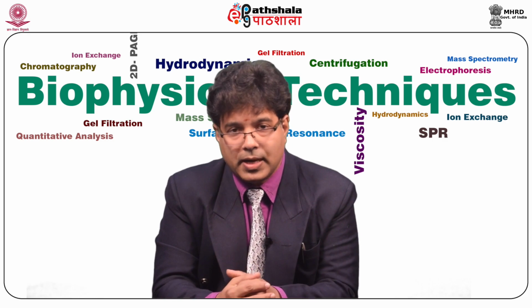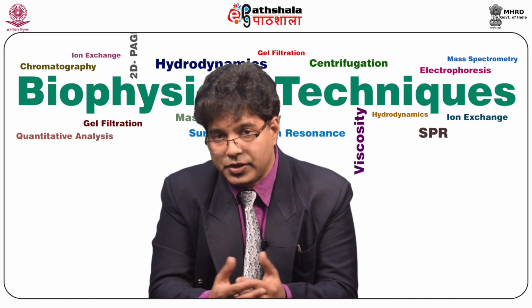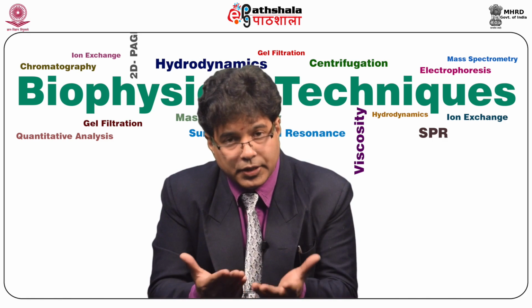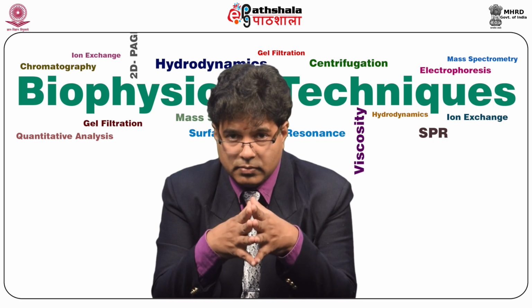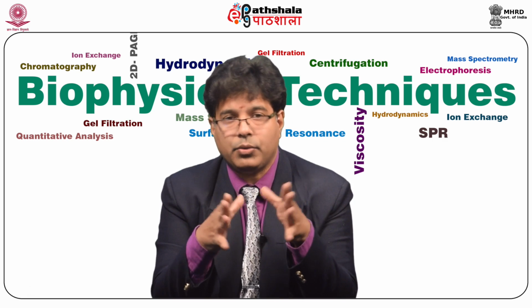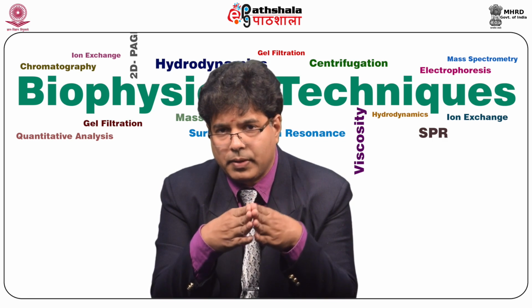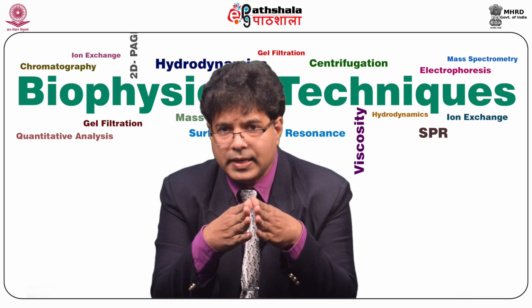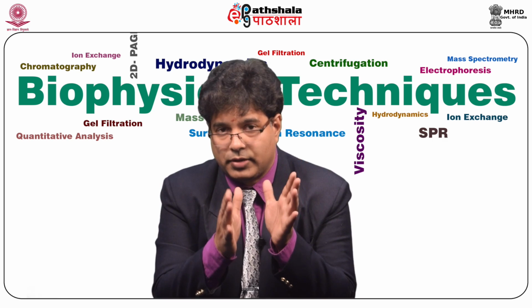While we compare different mass spectrometers, there are some fundamental aspects which we try to use to differentiate them. One is dynamic range, another one is mass accuracy. The dynamic range is a property of the mass spectrometer over which the linear response is observed for an analyte as a function of analyte concentration.